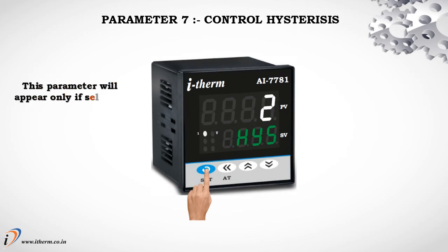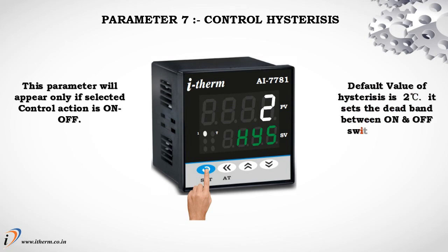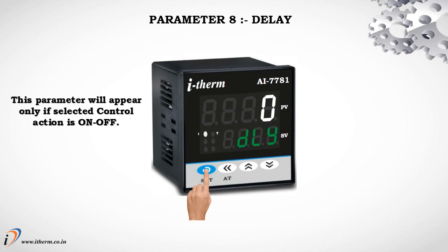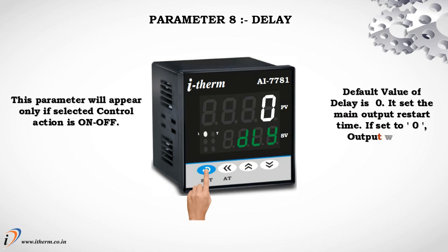Parameter 7 is Control Hysteresis. This parameter will appear only if the selected control action is ON-OFF. The default value is 2 degrees centigrade. It sets the dead band between ON and OFF switching of the output. Parameter 8 is Delay, which also appears only in ON-OFF mode. The default value of delay is 0. It sets the main output restart time. If set to 0, the output will be switched without delay.